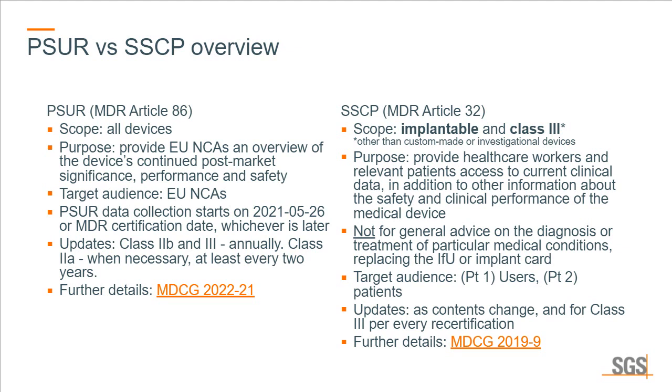So the PSUR, I already mentioned this, regulated by MDR Article 86. The scope is all devices. The purpose is for the competent authorities to have an overview of the device's continued post-market significance, performance, and safety. Target audience is just the competent authorities. The PSUR data collection started in 2021-5/26, or the MDR certification date, whichever is later. And it has to be updated periodically depending on the classes, and you can see the further details in the MDCG guideline.